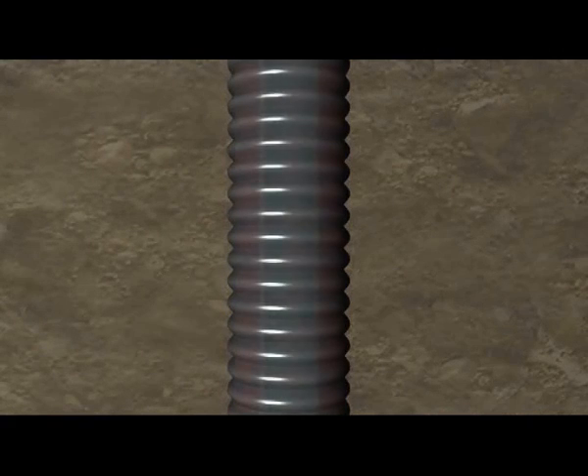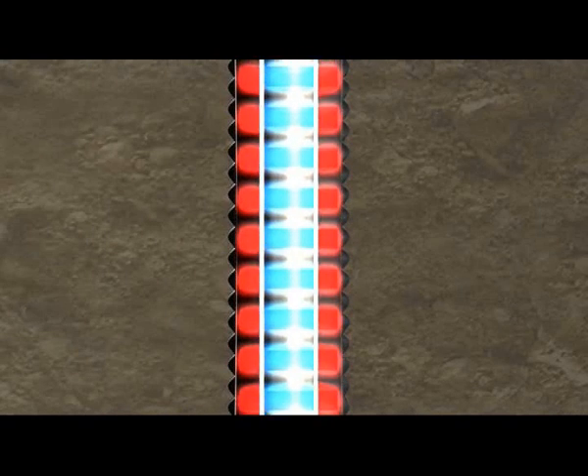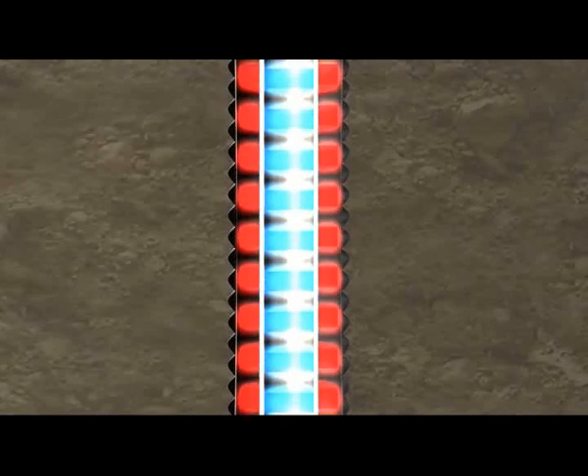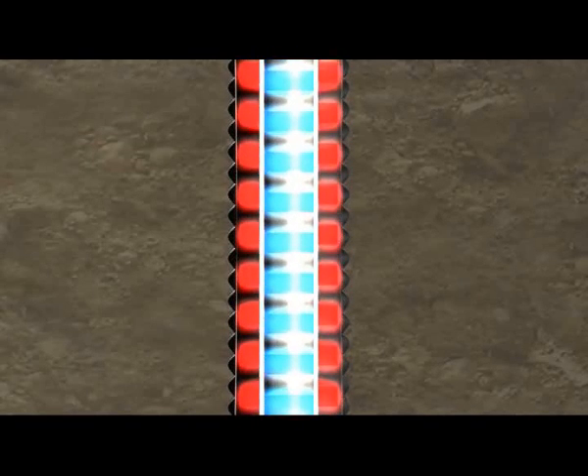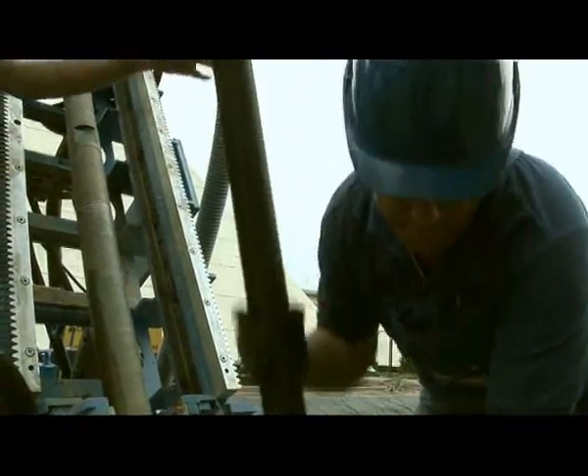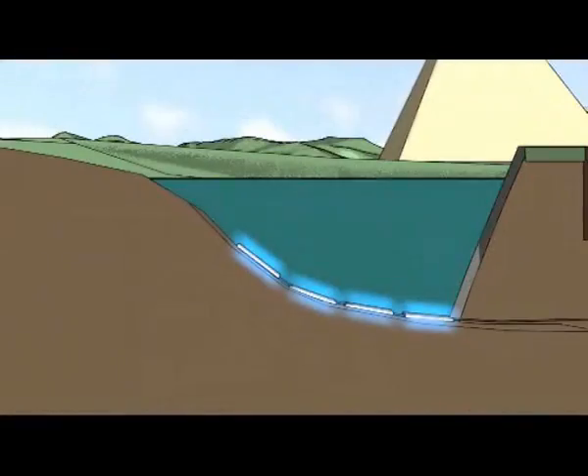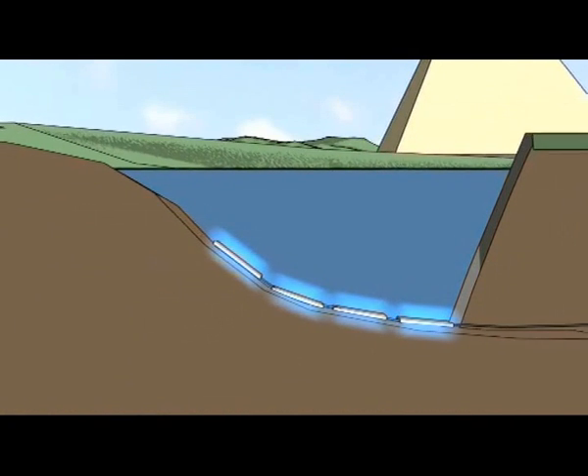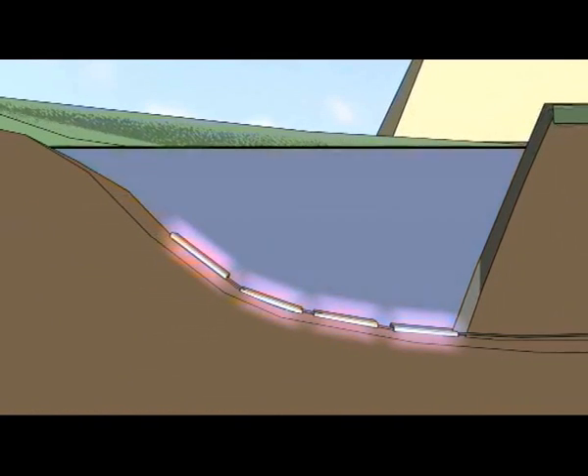The corrugated heat pipe design guarantees turbulent brine flow at a maximum heat pipe surface, which keeps the heat extraction performance high, even with low flow rates. Even water can be used as a heat transfer medium. The heat transfer medium circulating inside the heat pipe is pumped through a circuit without a heat pump and releases the heat via heating mats on the ground of the pond.